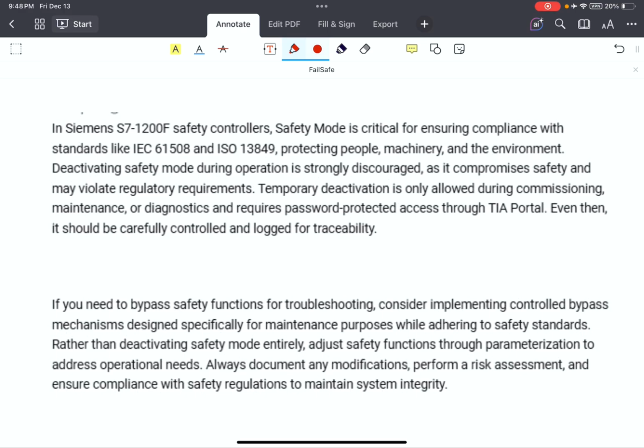In a Siemens S7-1200 safety controller, safety mode is critical for ensuring compliance with international safety standards, or possibly in some countries you may encounter more strict rules. The reasons for safety mode in PLCs are protecting people, machinery, the environment, and deactivating safety mode during operation is strongly discouraged. So it's not recommended as it compromises safety and may violate regulatory requirements. So this is important. Temporary deactivation is only allowed during commissioning, maintenance, or diagnostics, and requires password protected access through the portal. Even then, it should be carefully controlled and logged for traceability.